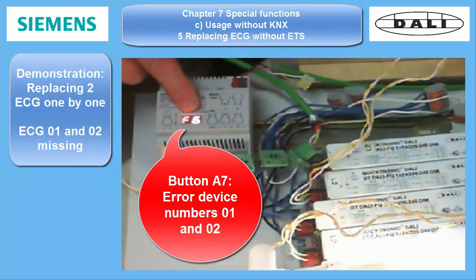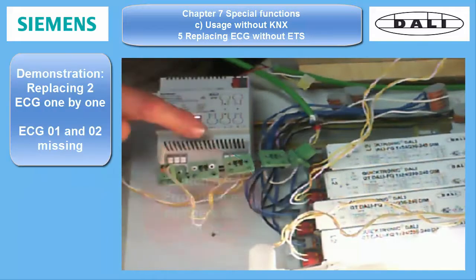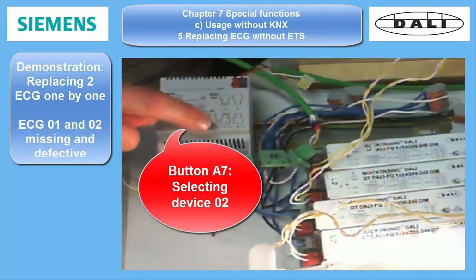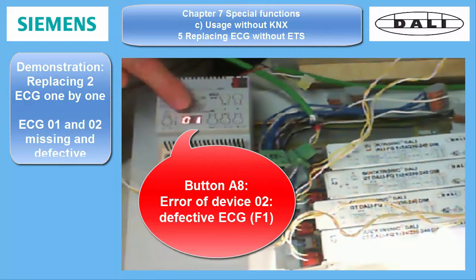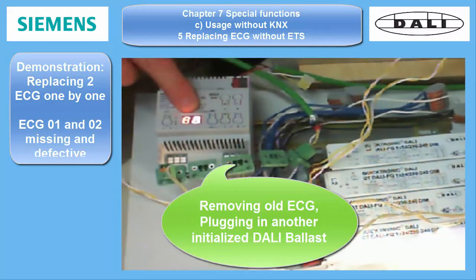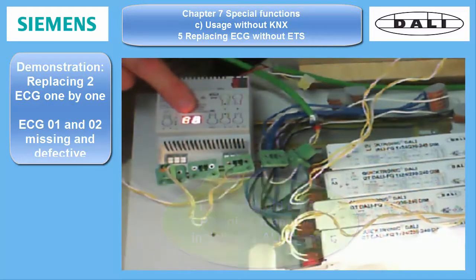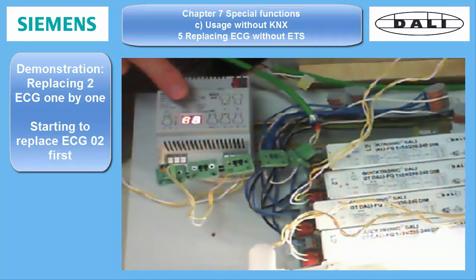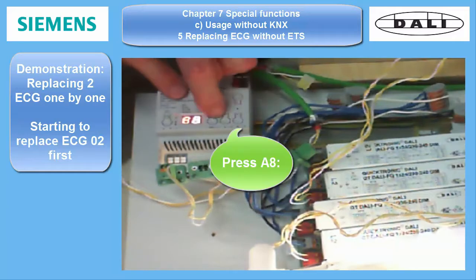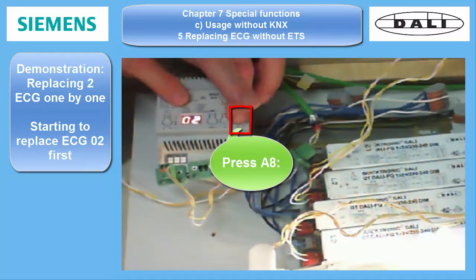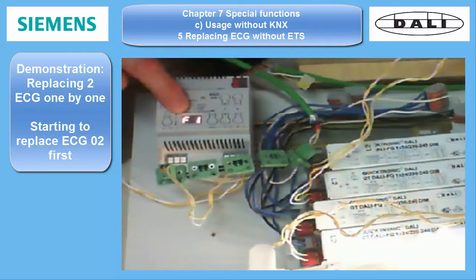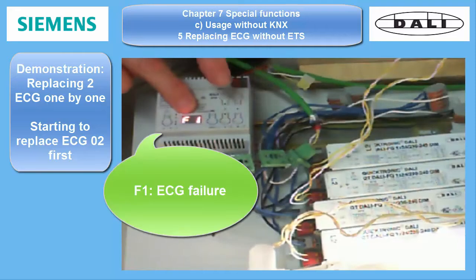To find out which device, press A7 up or down. It shows 02, which means ECG number 2. This is not the short address, but the order number in the parameters. Now, press A8 again. It shows error F1. That stands for ECG failure.